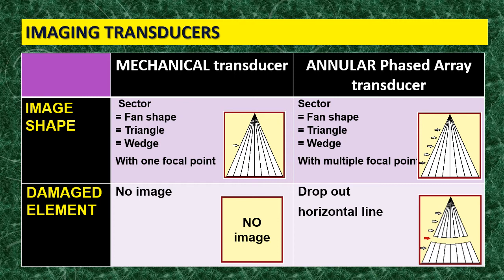What happens if the active element is damaged? In the mechanical transducer, with its single element damaged, you get no image at all. But in the annular phased array, if one of the active elements is damaged, you get a transverse horizontal dropout line — a line that runs from side to side of the image, coinciding with the focal point of the damaged element.